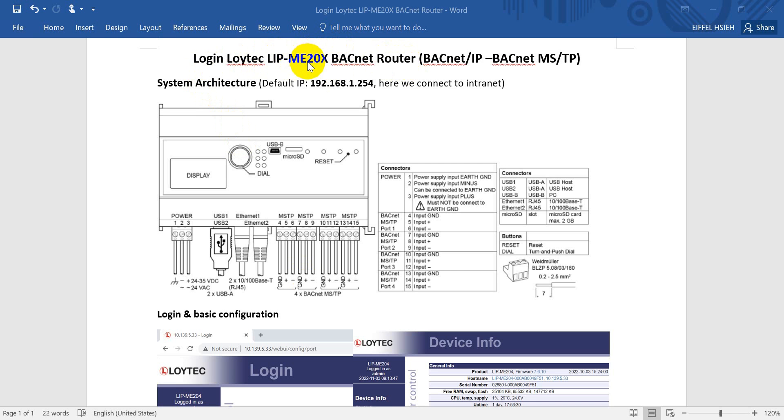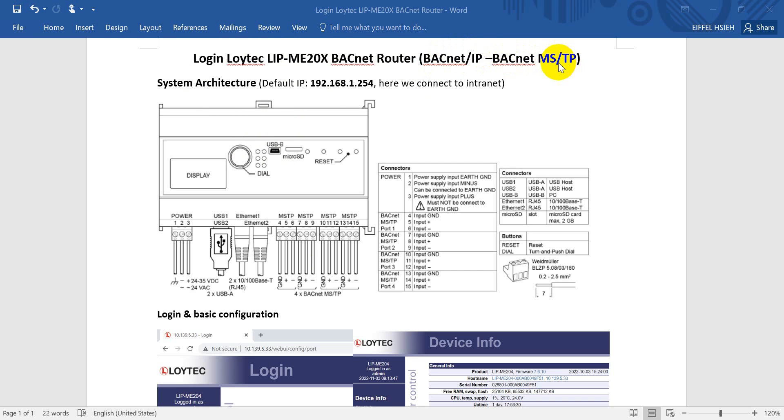The LIP Router has three main models: ME201, ME202, and ME204. Today's example is based on the ME204, and the purpose is to convert signals from BACnet IP to BACnet MS/TP. The default IP address of the Ethernet port is 192.168.1.254.